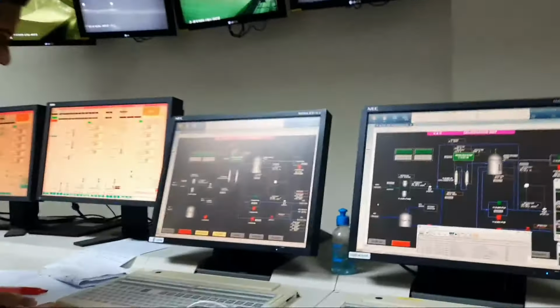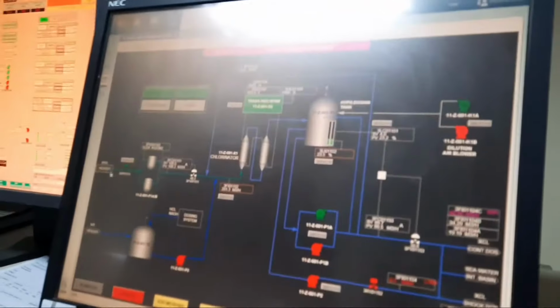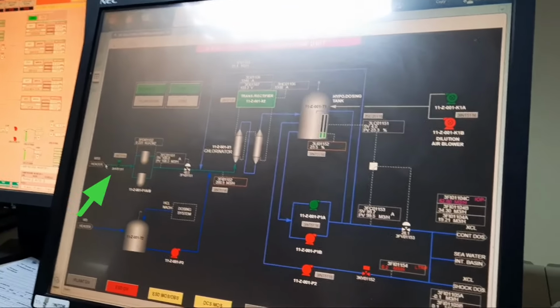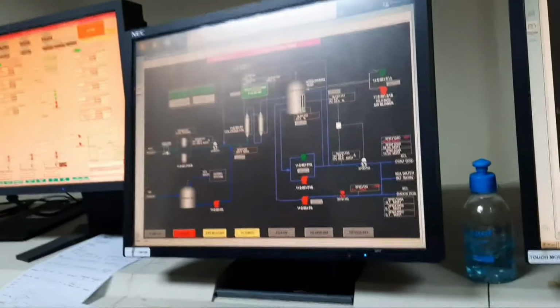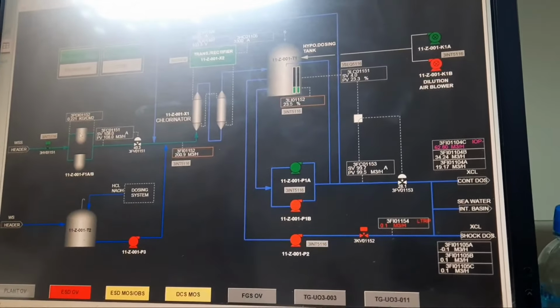Okay, this is our chlorination unit. Focus on this chlorination unit. We are using 120 meter cube of seawater from this line. And this is our self-cleaning strainer. We are removing 10%. So total flow 120 meter cube; if you calculate 10%, it comes to 12 meter cube.